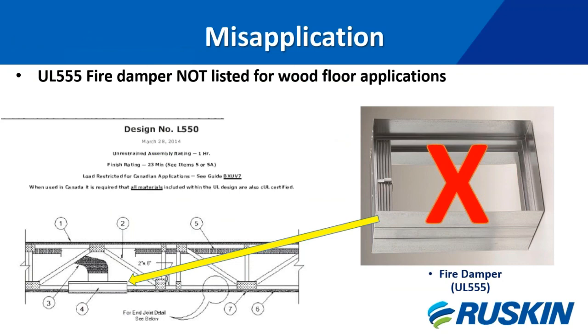One common misapplication is using a horizontal curtain fire damper in place of a CFD. This is not a UL listed installation and needs to be avoided at all costs. If you use a curtain damper in this application, you may be required to remove the dampers and replace them with the proper model for that application.